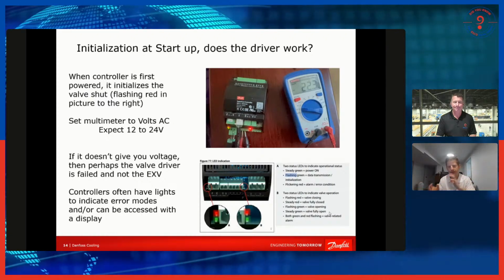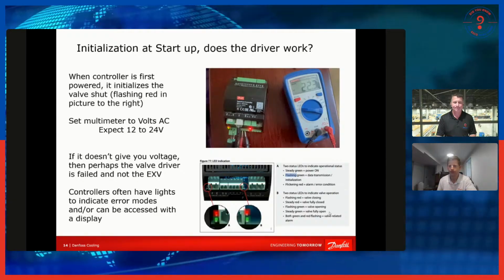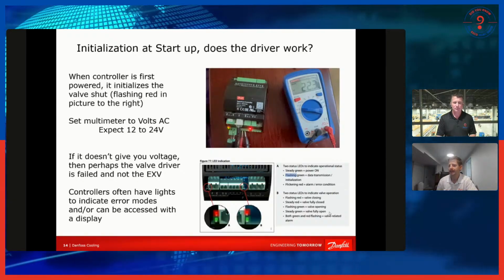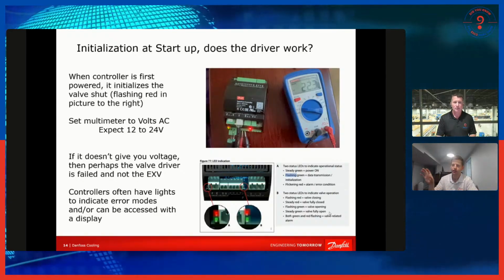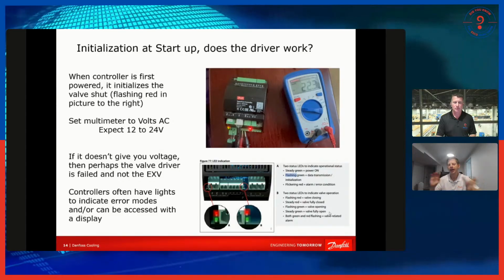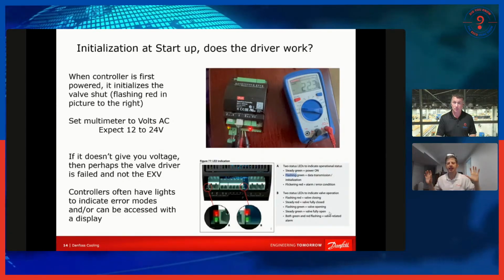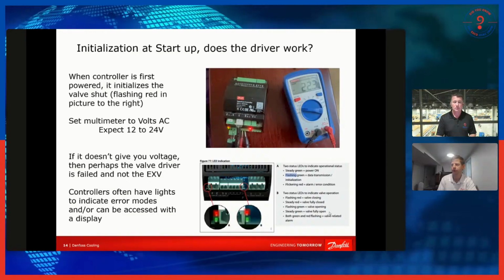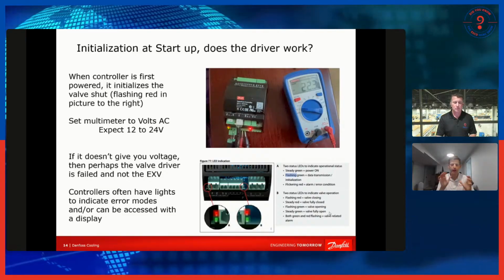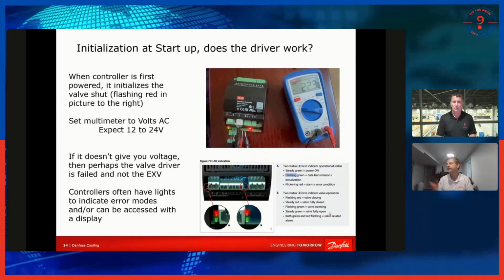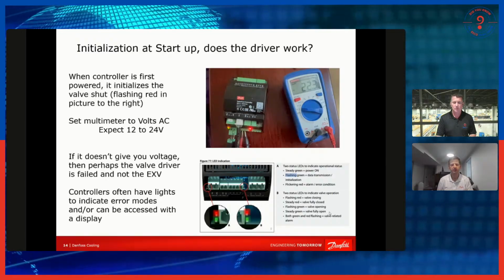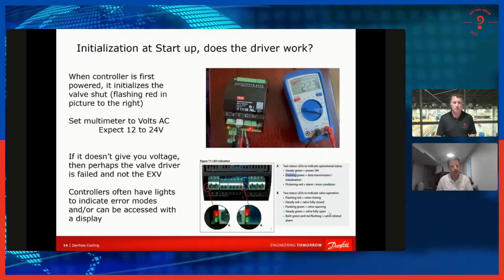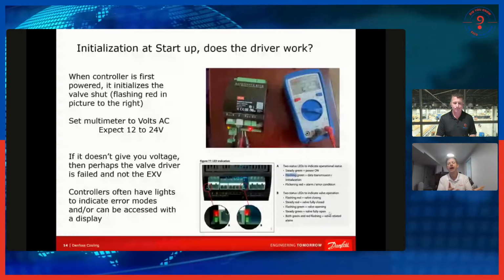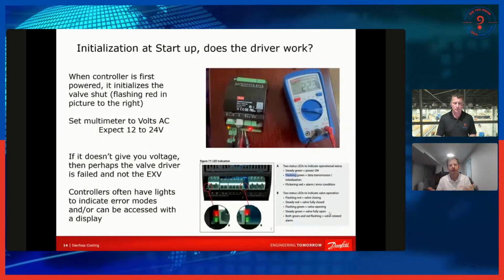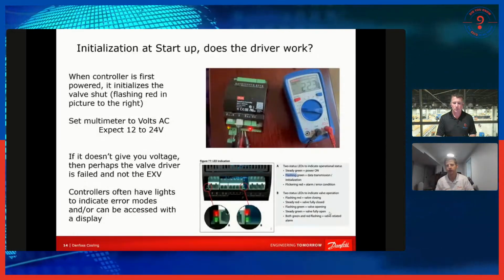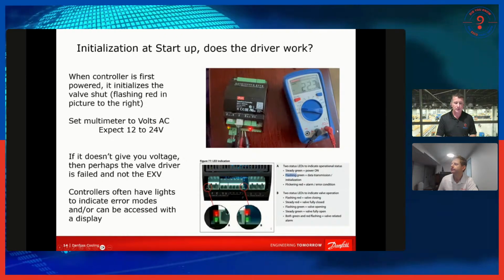They're their own independent thing, and it's kind of the way it is. But a lot of these controllers do have lights on them to flash and give you some sort of indication of what's happening. And that's a good place to look, and it helps you figure out what's working and what's not working. If you never see any lights light up on one of these boards, it gives you a good indication the board doesn't work. Either there's no power going to it, or it's burned and died, and the power's not doing anything to it. Yeah, completely makes sense.